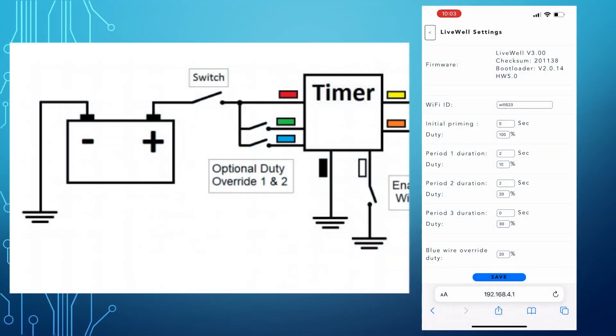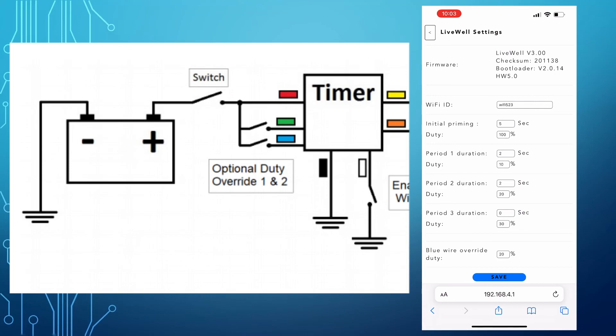Let's talk about optional overrides. The blue wire allows you to externally override the output of the timer. For example, if you want the timer to produce 50% duty output without cycling, configure the 50% for the blue wire in the timer's configuration. You can connect the switch between the blue wire and power. When you flip the switch the output will be set to 50% duty until you turn the switch off.